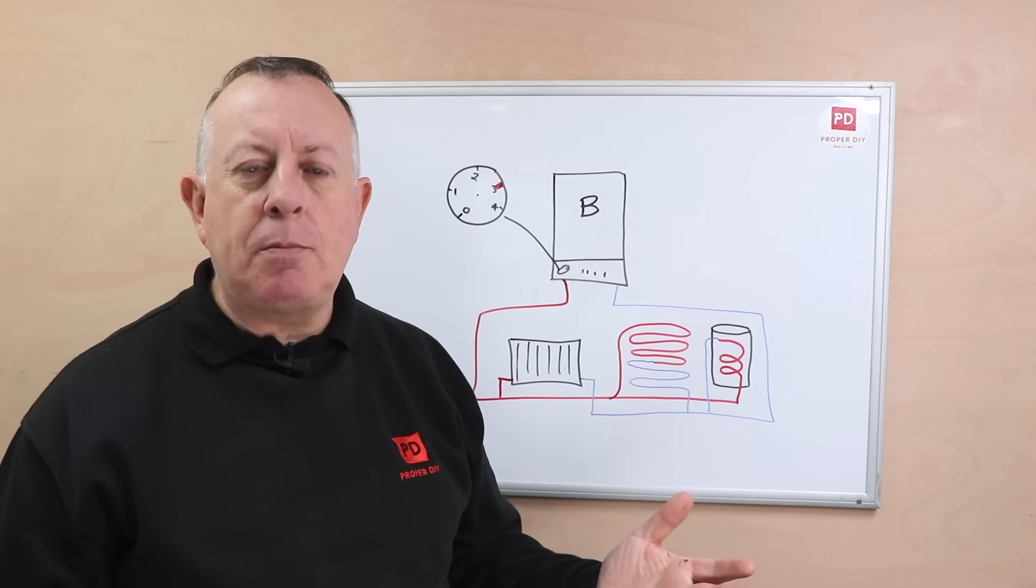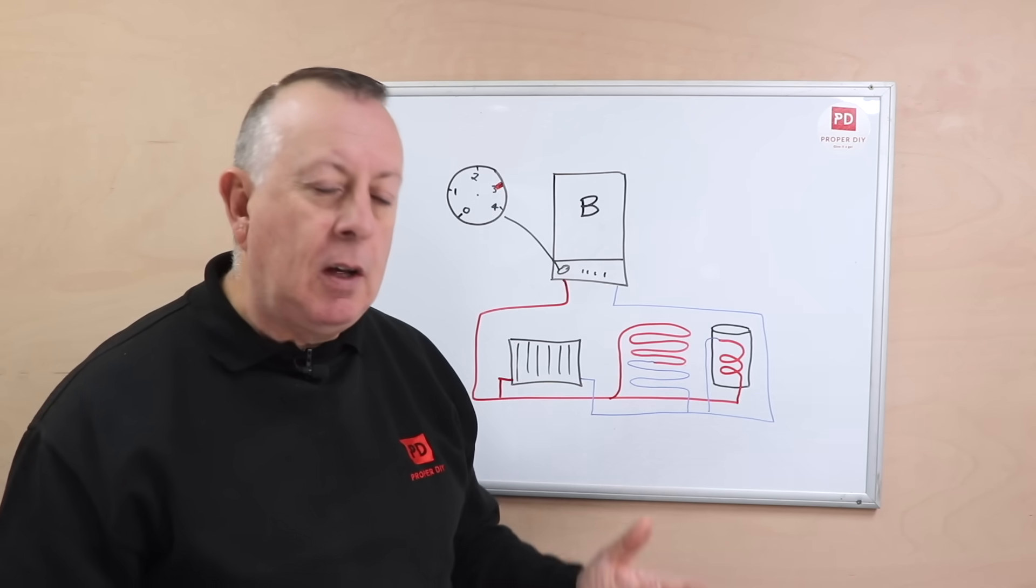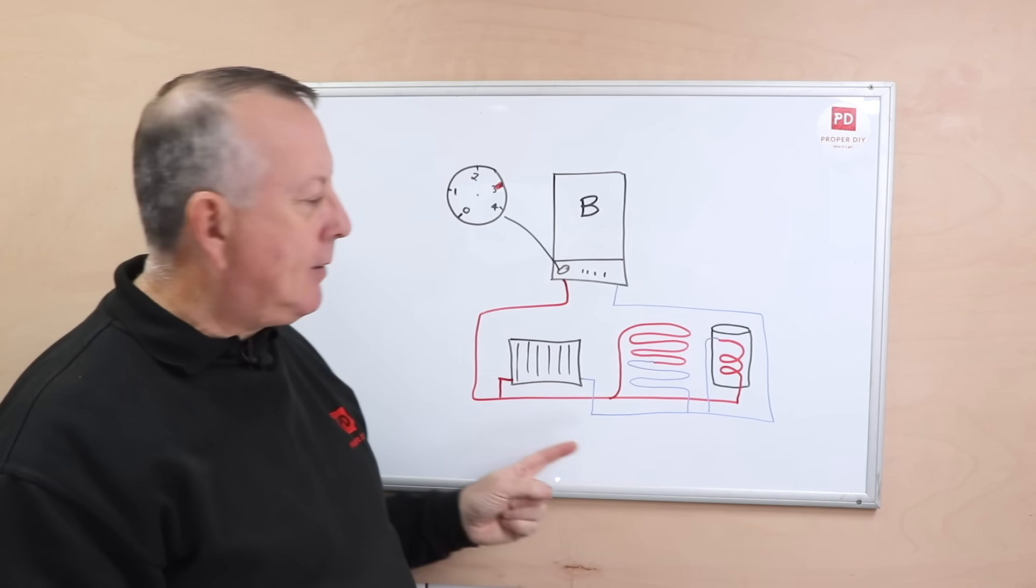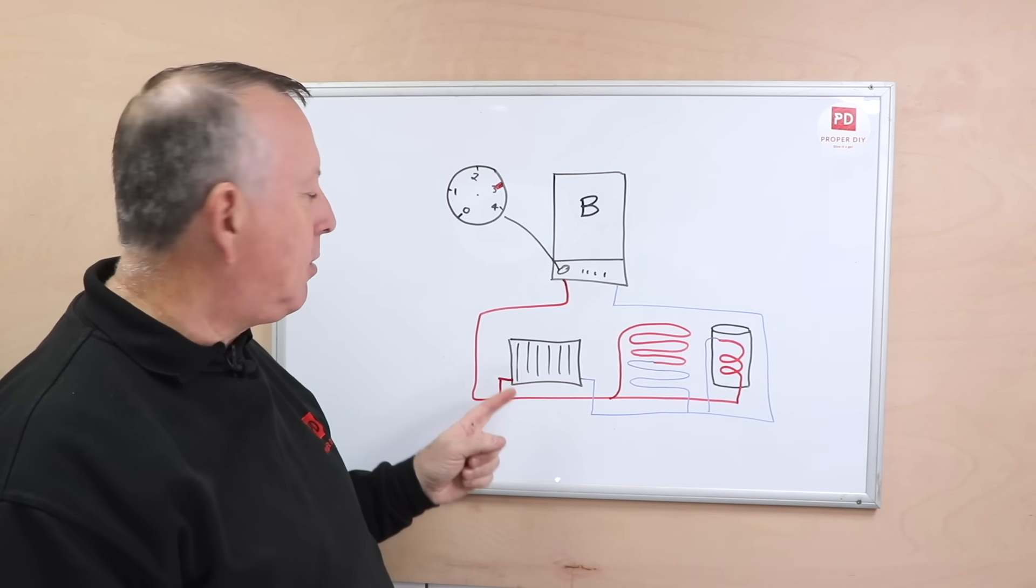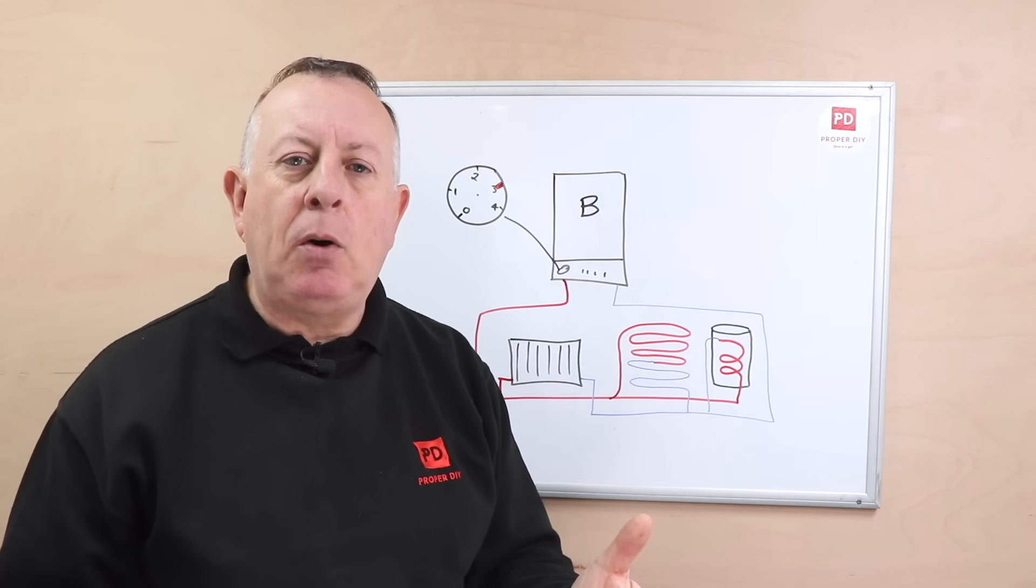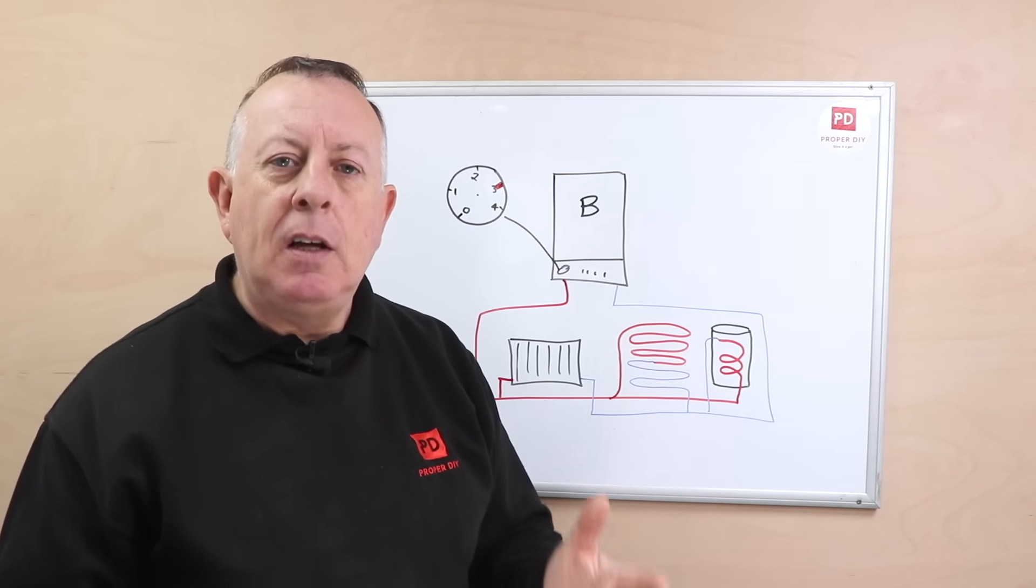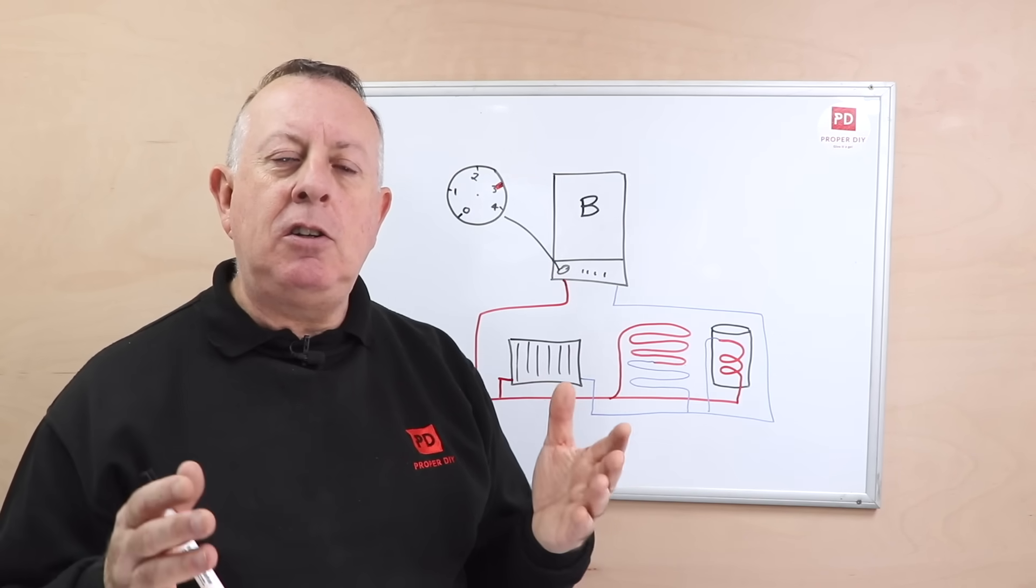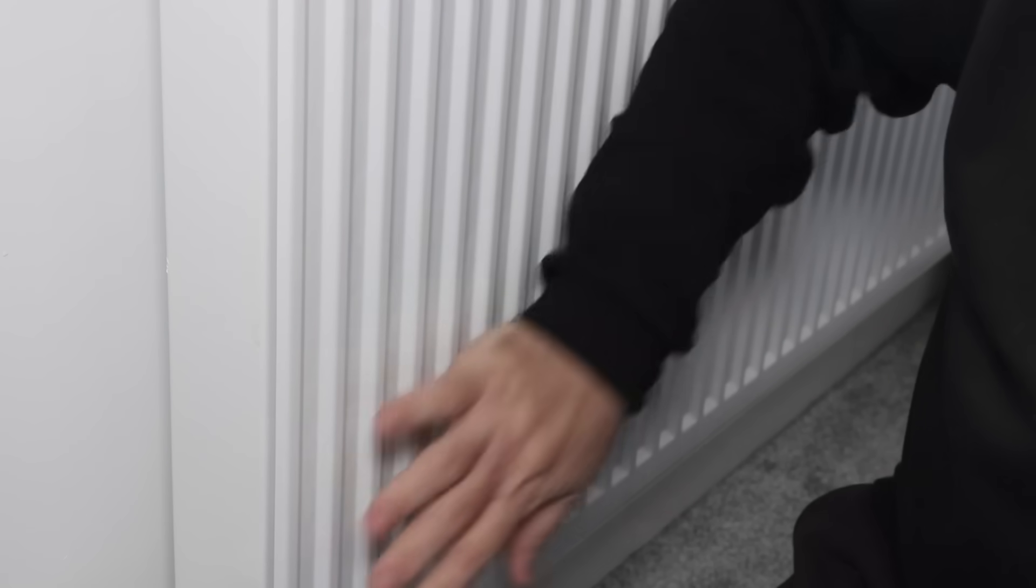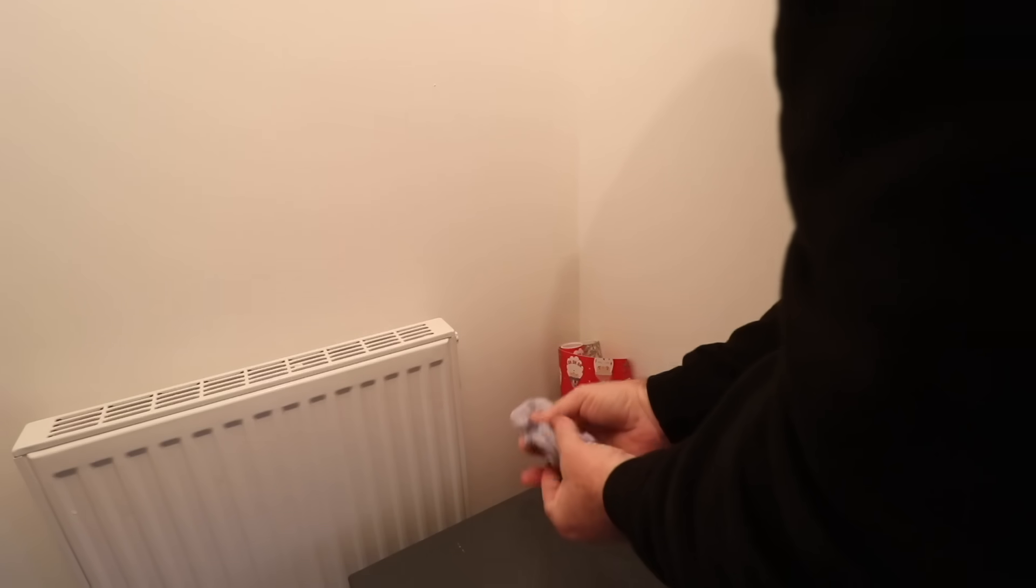So where do we lose the pressure when we're not bleeding radiators? Well the first obvious cause is if we've got any leaks in this system - any leaks around radiators or any of our pipework. So it's really important if you think you've got a problem that you go around your house and you look at each radiator and all the pipework you can find looking for any leaks or drips.